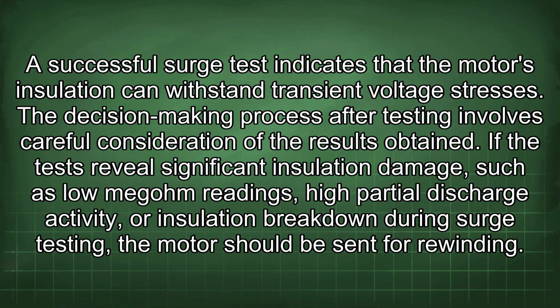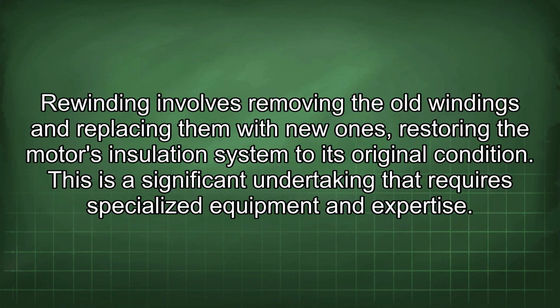The decision-making process after testing involves careful consideration of the results obtained. If the tests reveal significant insulation damage, such as low megohm readings, high partial discharge activity, or insulation breakdown during surge testing, the motor should be sent for rewinding. Rewinding involves removing the old windings and replacing them with new ones, restoring the motor's insulation system to its original condition. This is a significant undertaking that requires specialized equipment and expertise.